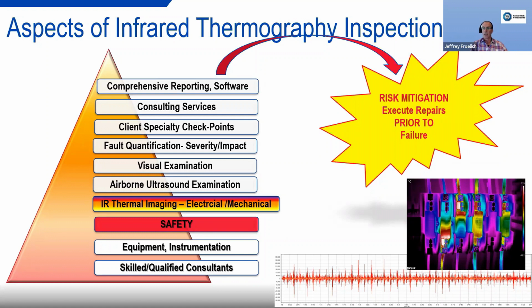They may get a very good quality maintenance troubleshooting camera, and it'll do a great job for them. Of course, accuracy will go up and resolution with the level of your equipment. Then, of course, safety is paramount. That's what this whole webinar is about. It's got to be a critical component of this because you're working on the equipment live while energized. It's got to be live, energized, and loaded.